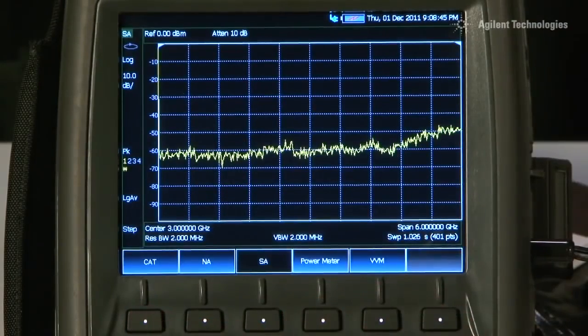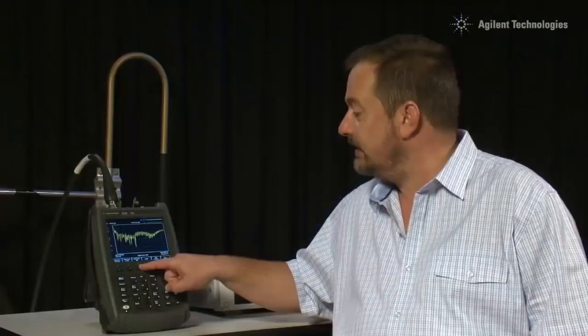We just disconnect the cable from the transmitter at the bottom of the mast and connect it directly to the FieldFox. So I will press Mode and select CAT for cable and antenna test and return loss in dB that is already selected.